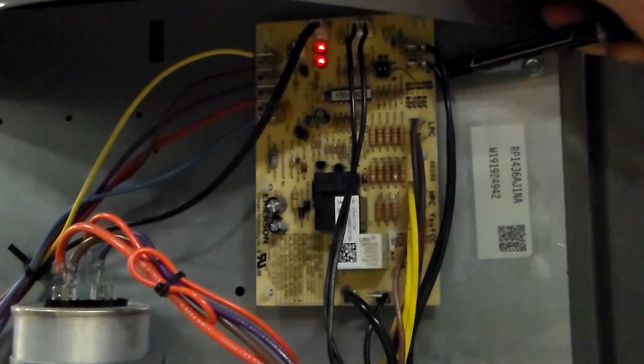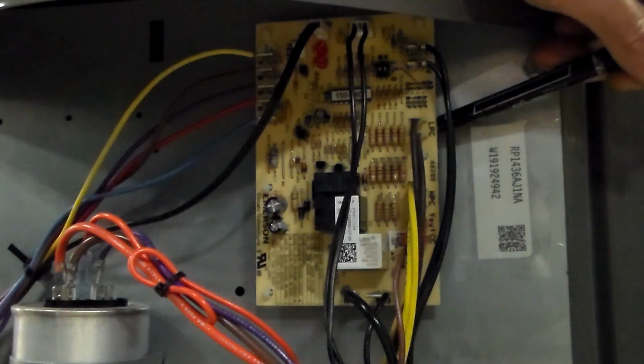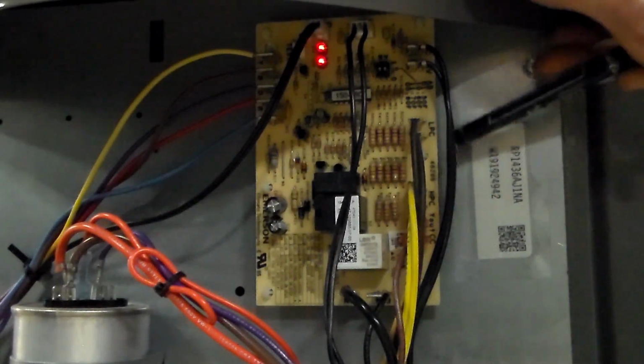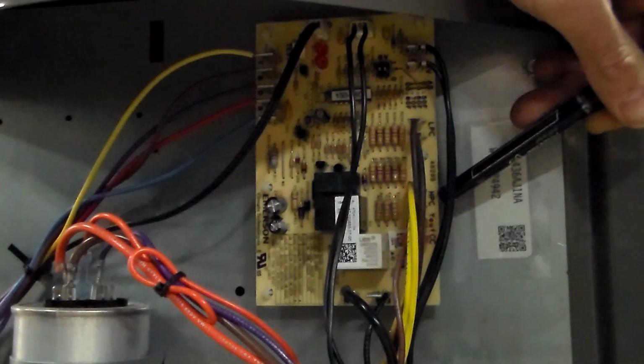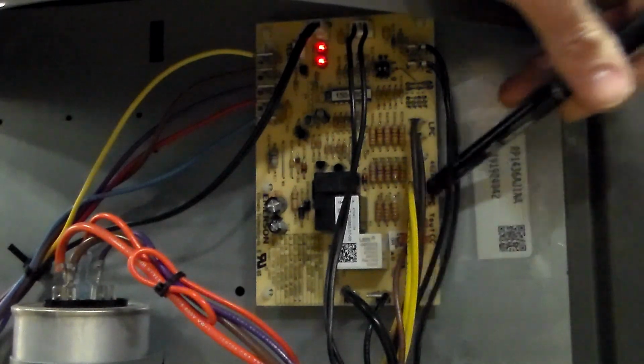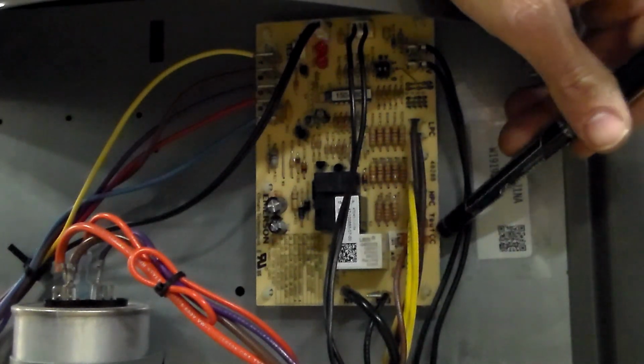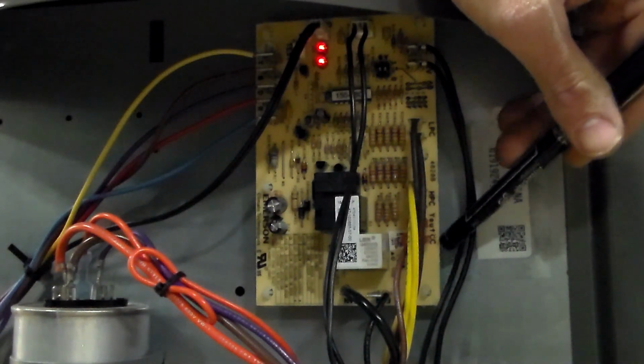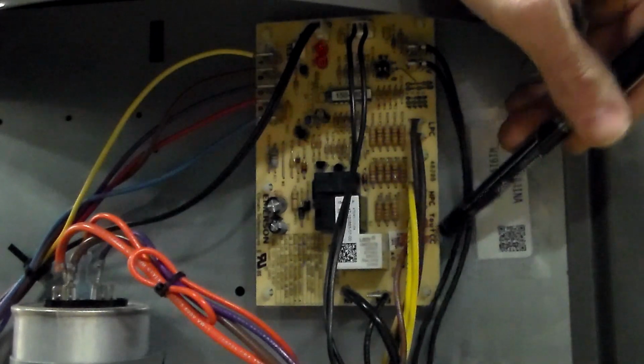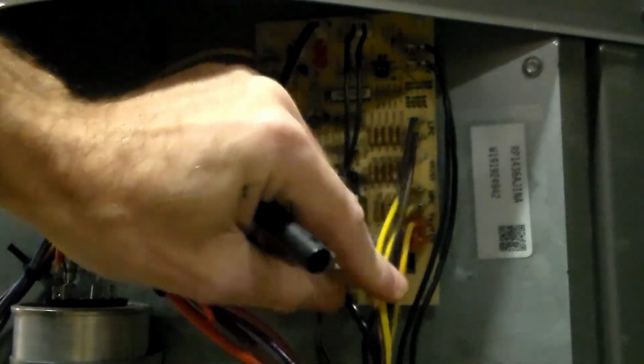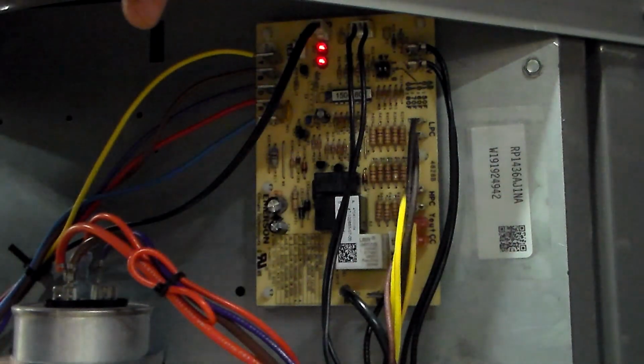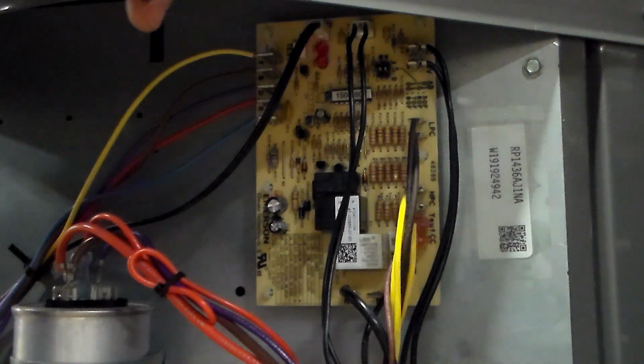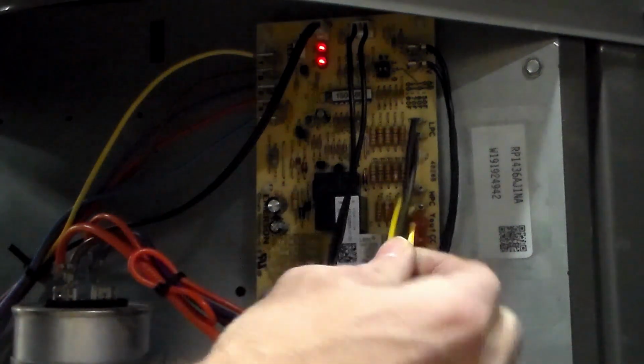So that's clearly hot and common for our reversing valve. And then we have LPC and HPC, which is our low pressure and our high pressure sensors. And then on the very bottom here, we have our Y out CC. So that just means that's your power to your contactor. That's your 24 volts coming out to your contactor. And again, on the contactor end of things, it doesn't care which direction you poke those wires in. One's going to be hot, one's going to be common, and the contactor doesn't care which one's which. So there's nothing you can do wrong there.